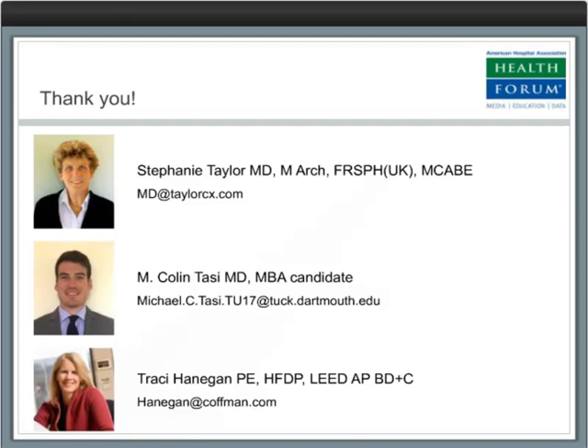Ms. Hannigan, do you want to take that one? Sure. Well, I could joke that it depends on where you grow up and what part of the country you're used to working in. In the Pacific Northwest we deal a lot more with heating, and it's not that humid here, while people in the Southeast and Midwest tend to encounter a lot more humidity coming in the indoor air. But when you're talking especially about operating rooms, it doesn't matter—they're all air-conditioned spaces. I think it's more straightforward to add humidification to a space you're trying to heat, where the air is already dry and you're just adding moisture. When you're air conditioning, you're trying to cool the air, which causes condensation—you're pulling moisture out and then have to reintroduce it. So it's a more challenging situation for a designer doing air conditioning to try to maintain that relative humidity range.